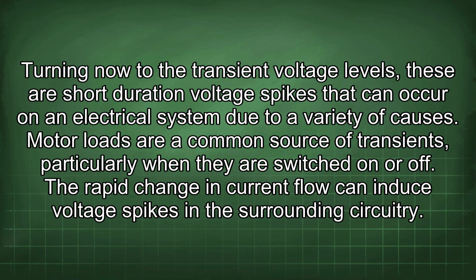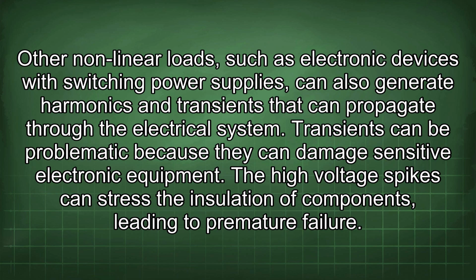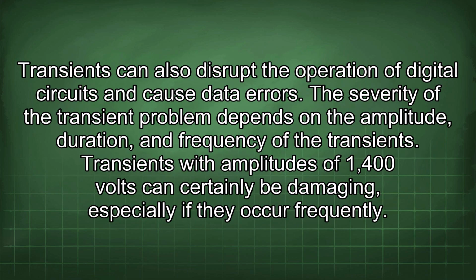Motor loads are a common source of transients, particularly when they are switched on or off. The rapid change in current flow can induce voltage spikes in the surrounding circuitry. Other nonlinear loads, such as electronic devices with switching power supplies, can also generate harmonics and transients that can propagate through the electrical system. Transients can be problematic because they can damage sensitive electronic equipment. The high voltage spikes can stress the insulation of components, leading to premature failure. Transients can also disrupt the operation of digital circuits and cause data errors.